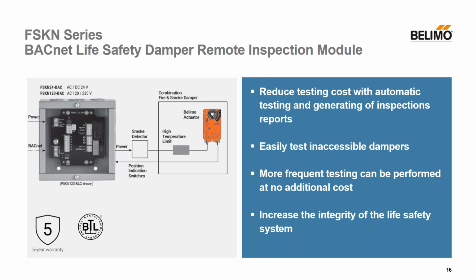Upon a test command, the actuator power is cut, allowing it to spring the damper closed. The actuator is then again powered, and it drives the damper open to its normal operating position. Auxiliary switches on the actuator or the damper blades are monitored to observe the correct damper blade position in each mode of test and operation. And upon completion of the test cycle, a pass or fail message is delivered via the BACnet controller.